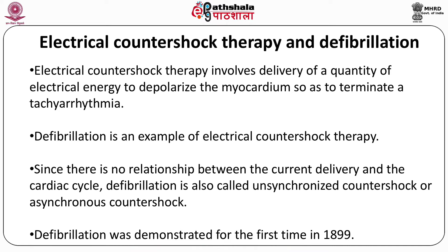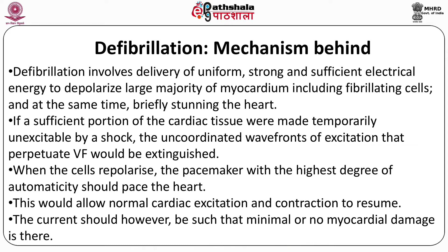Defibrillation, mechanism behind. Defibrillation involves delivery of uniform, strong and sufficient electrical energy to depolarize a large majority of myocardium including fibrillating cells and at the same time briefly stunning the heart. If a sufficient portion of cardiac tissue were made temporarily unexcitable by a shock, the uncoordinated wavefronts of excitation that perpetuate ventricular fibrillation would be extinguished. When the cells repolarize, the pacemaker with the highest degree of automaticity should pace the heart. This would allow normal cardiac excitation and contraction to resume. The current should however be such that minimal or no myocardial damage is there.